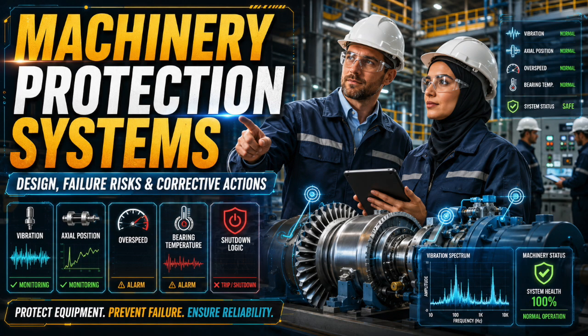And this is where many engineers make their first serious mistake. They think the job is to select instruments. But machinery protection is not instrument selection alone. It is failure mode thinking converted into hardware. You are not just asking, what sensor should I install? You are asking, what machine failure am I trying to detect? How quickly can it develop? What signal proves it is happening? What signal could mislead me? And what should the system do when that signal crosses the danger boundary? That is the mindset. That is the difference between monitoring and protection.